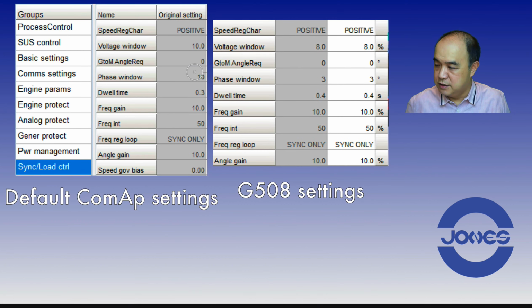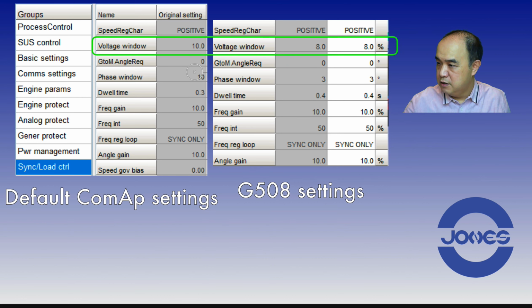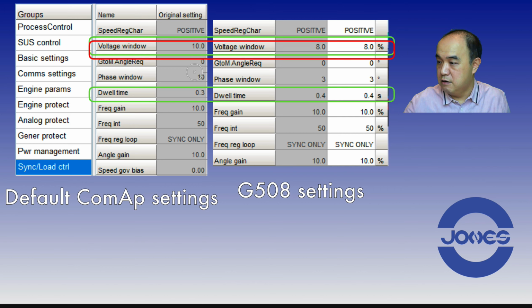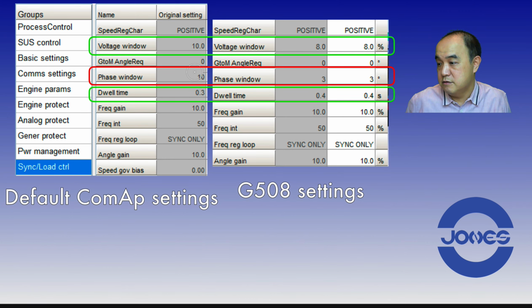If you take a look at the default ComAp settings, on the left-hand side, you can see the voltage window by default is 10%, and the dwell time is 0.3 seconds. The phase window that we set from ComAp, from factory, is 10 degrees, which is quite a bit wider than 3 degrees. But anyway, the settings on the genset on site was at 3 degrees.